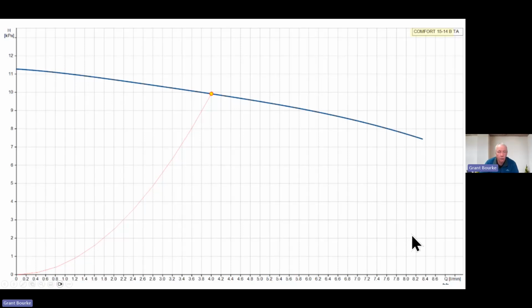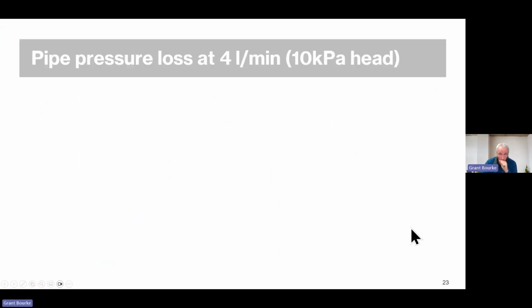So we've got the Grundfos Comfort. We've checked that our units are in kilopascals and our flow rates in litres a minute. And so we've picked the midpoint of the curve, and we've got roughly 4 litres a minute, and it's going to do about 10 kPa. So what we're going to do is we need to work out our pipe layout, what the pipe pressure loss is going to be at that midpoint of the curve. Now, hydraulic engineers, if you're going to get them to do this for you, they'll have software that'll take care of this. This is the manual way to do it on your kitchen table, but it works just fine for simple jobs.